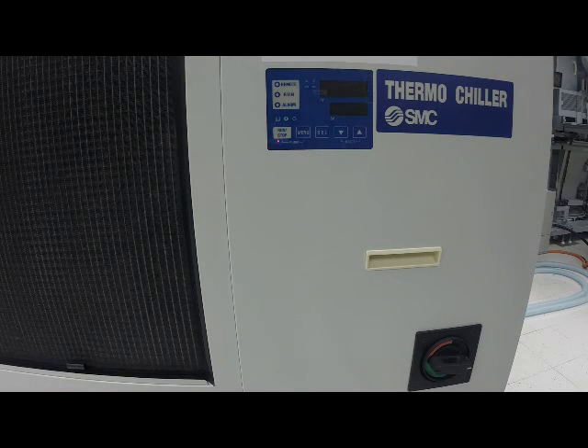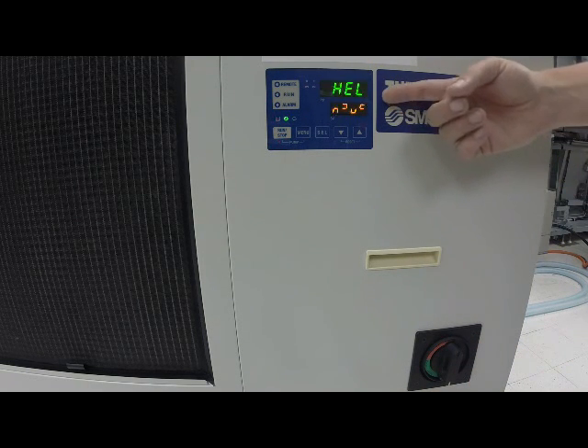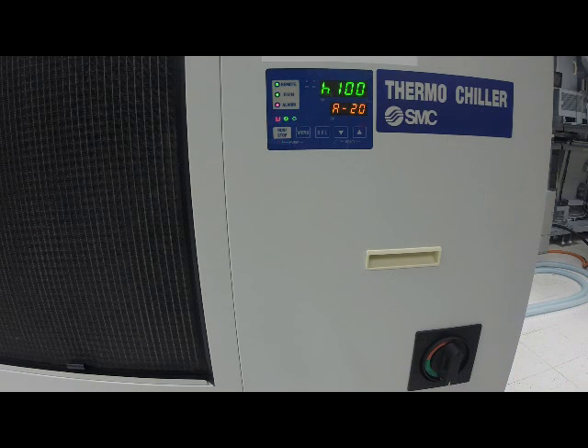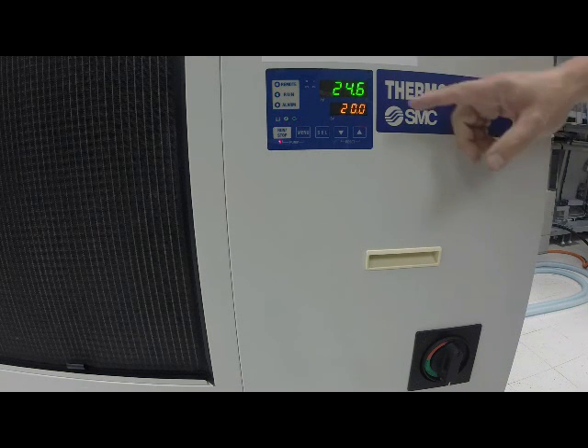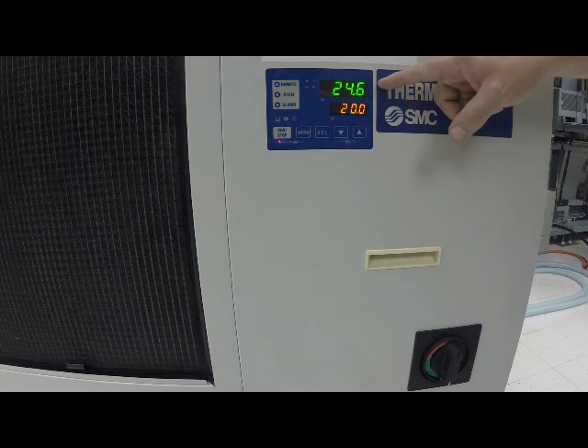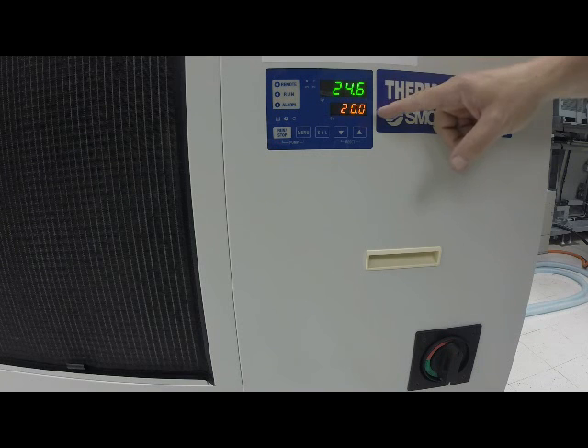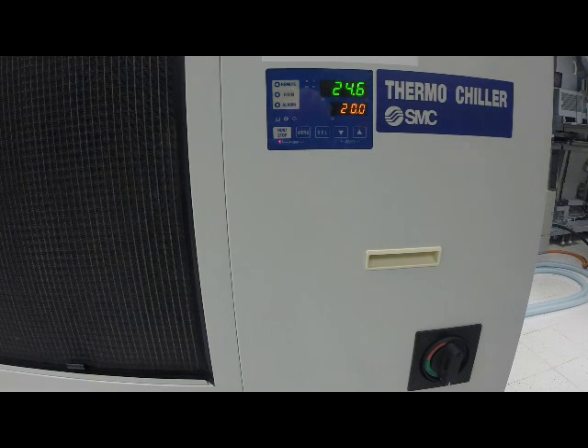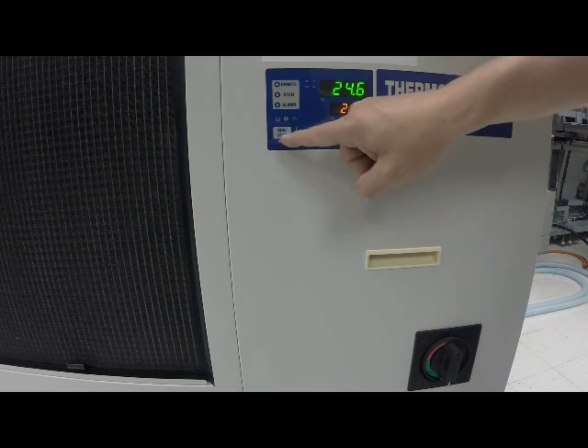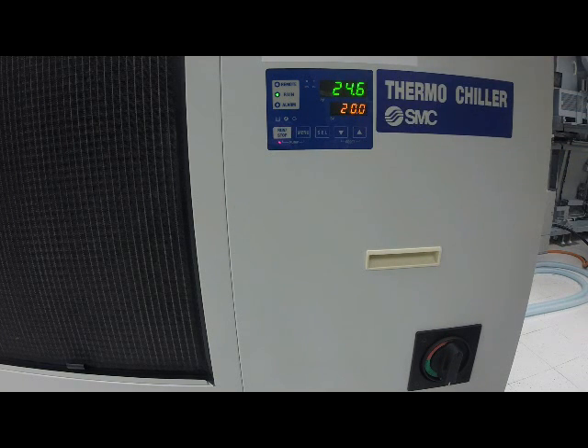To power on our chiller unit, turn your power breaker to the on position. You'll receive a welcome message first on the panel, and it will change. Once it changes, this is the present value of your cooling liquid in centigrade, and below that is the set value. Once you've come up to this point, press the run button and circulation will start.